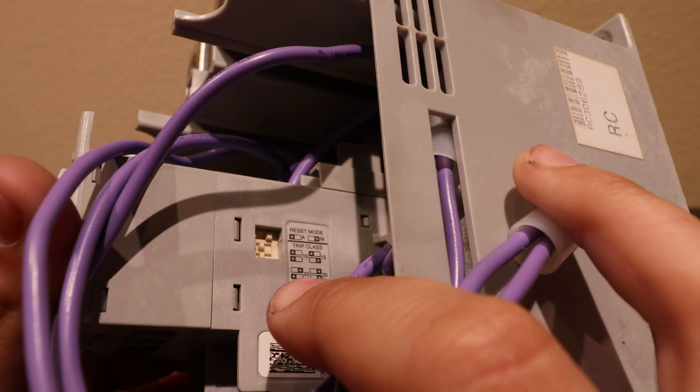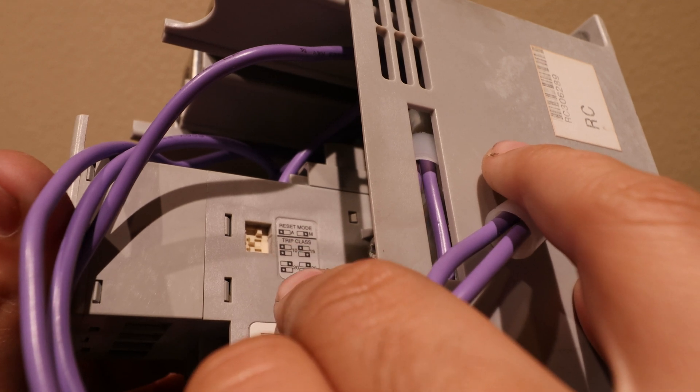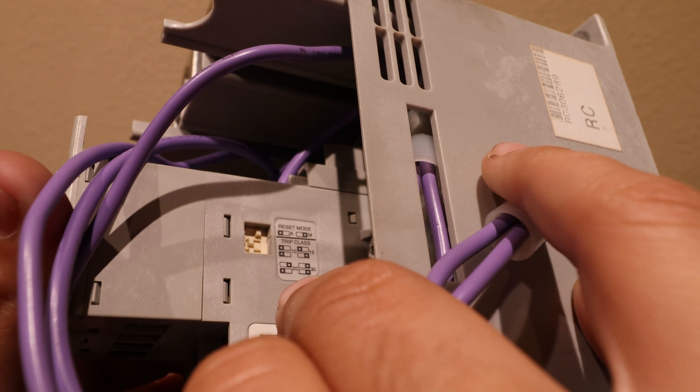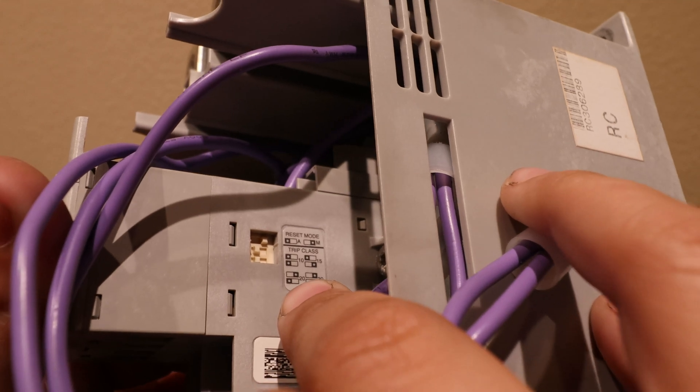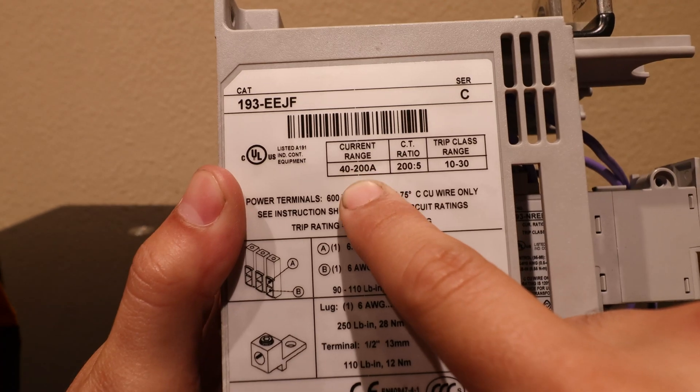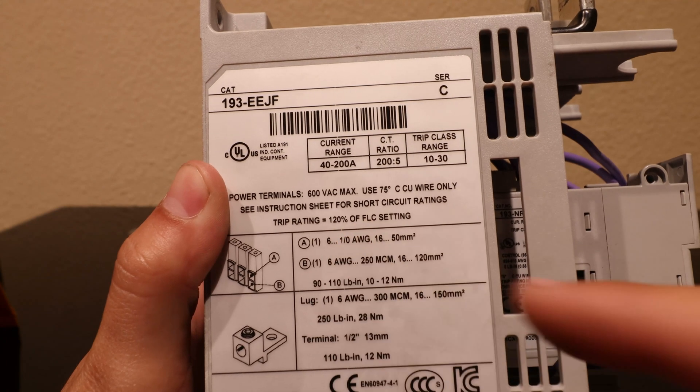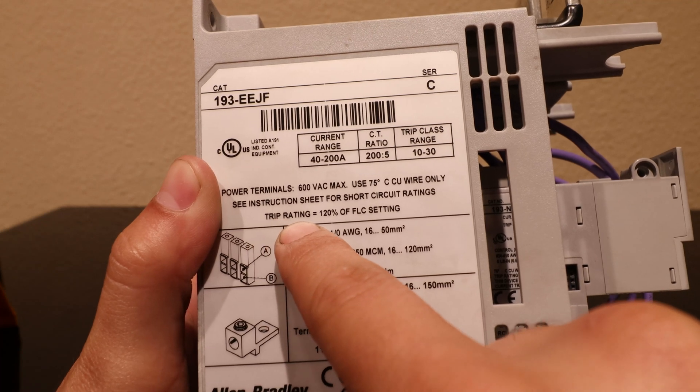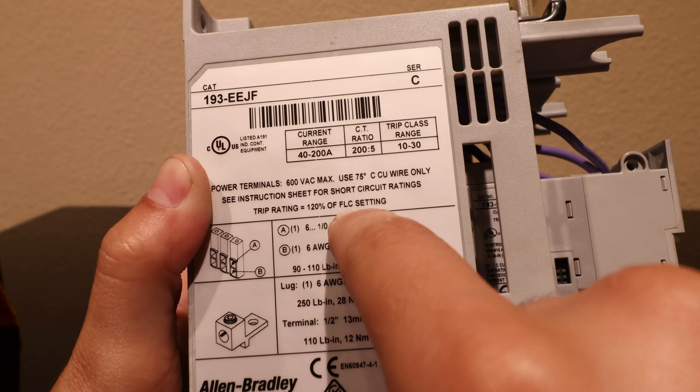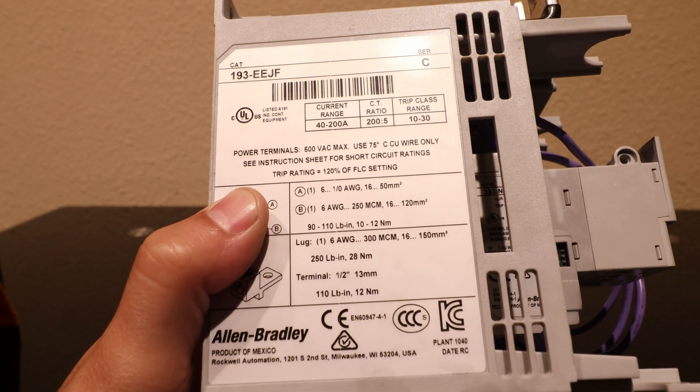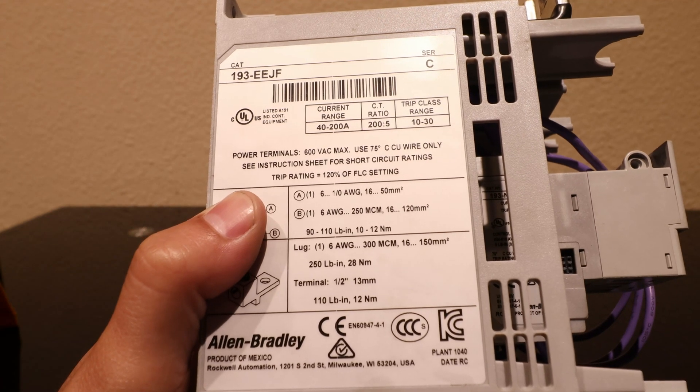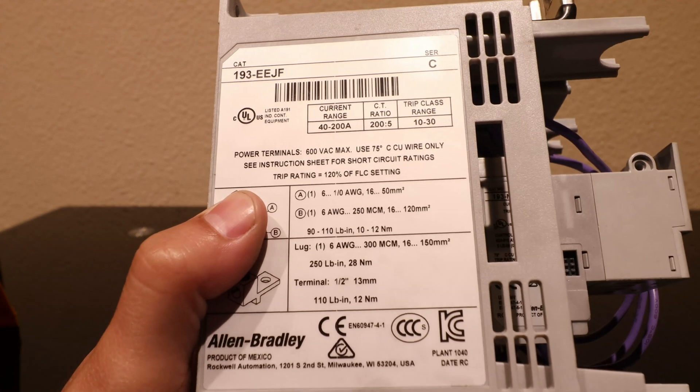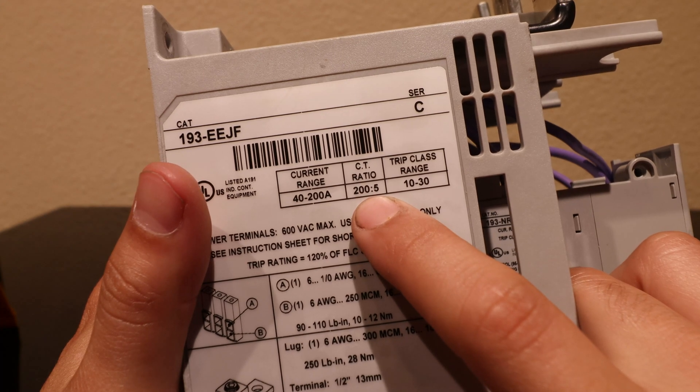It will trip the overload in an overcurrent situation based on the trip class setting which is set here on the inside of the overload. Two things we need to go over - the reset mode automatic versus manual, but also the trip class. There are trip classes of 10, 15, 20, and 30. This overload has a settable trip class. Whatever setting you set this, let's say the motor full load current is 180, you set it to 180. It actually trips at the trip rating, which is 120% of the full load current setting. So if you set it at 180, it will not trip until 216 amps, but only if the motor remains at 216 amps for a certain amount of time, and that's related to the trip class.